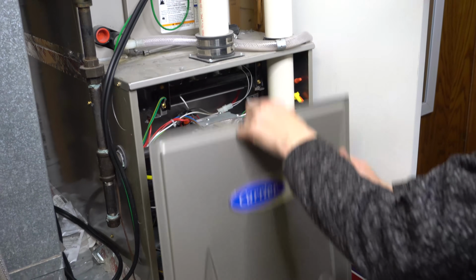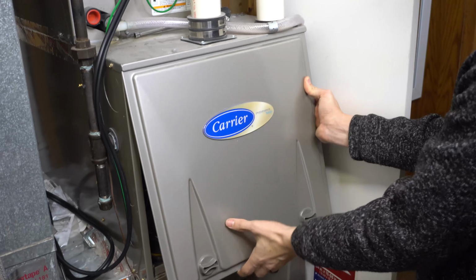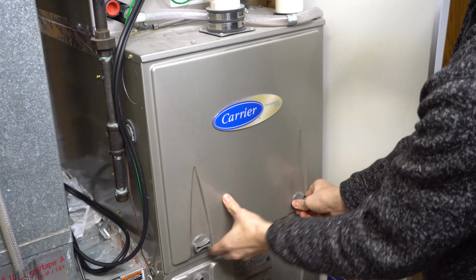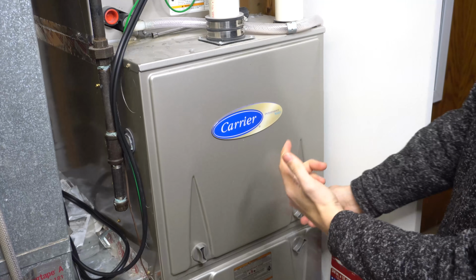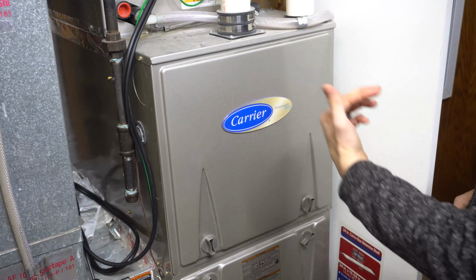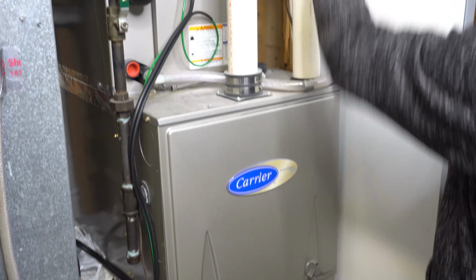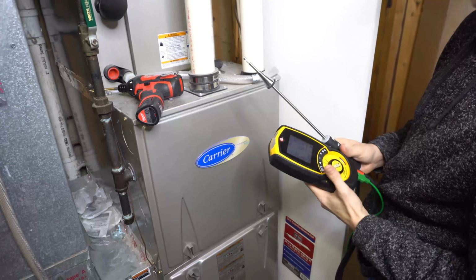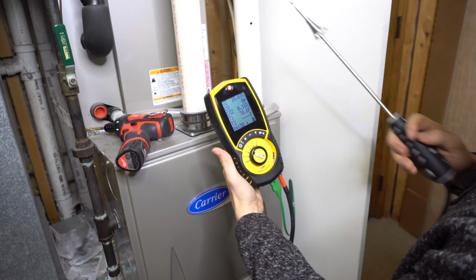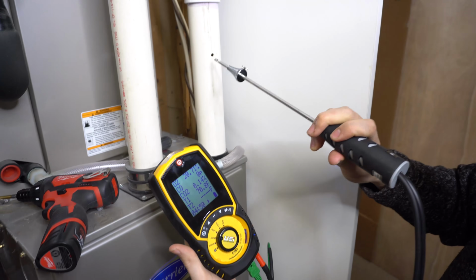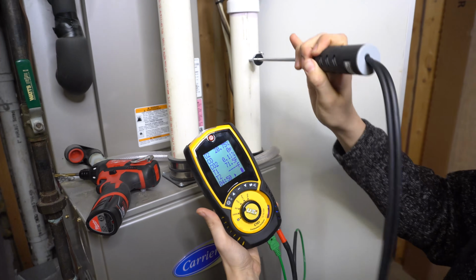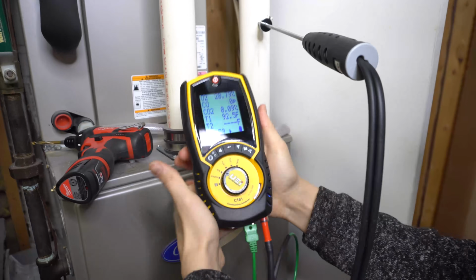So let's put the door back on and fire the furnace up and take my readings for the low stage, and then I'll wait for it to go into the high stage and we'll take another reading on the high stage. Okay, so the furnace has been running for a couple of minutes now, and I already have my analyzer fired up. Let's stick my probe in and see what kind of readings we get on a high efficiency furnace.